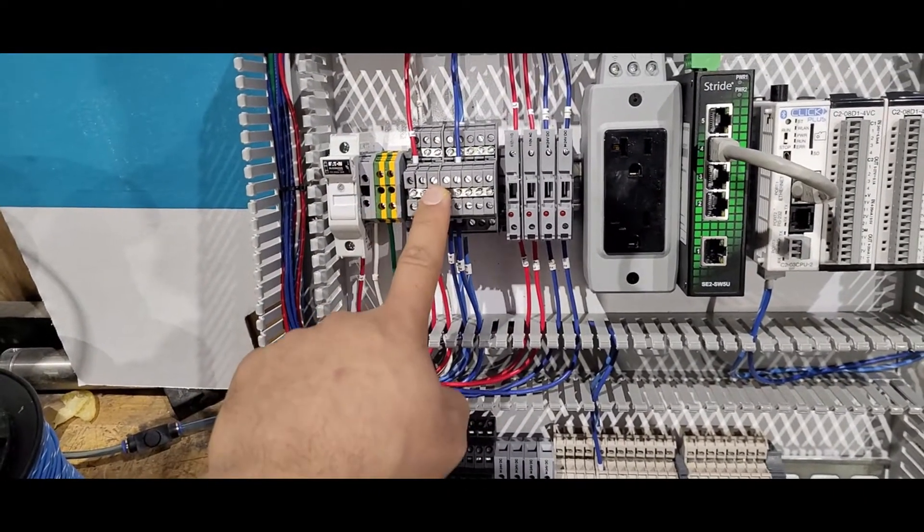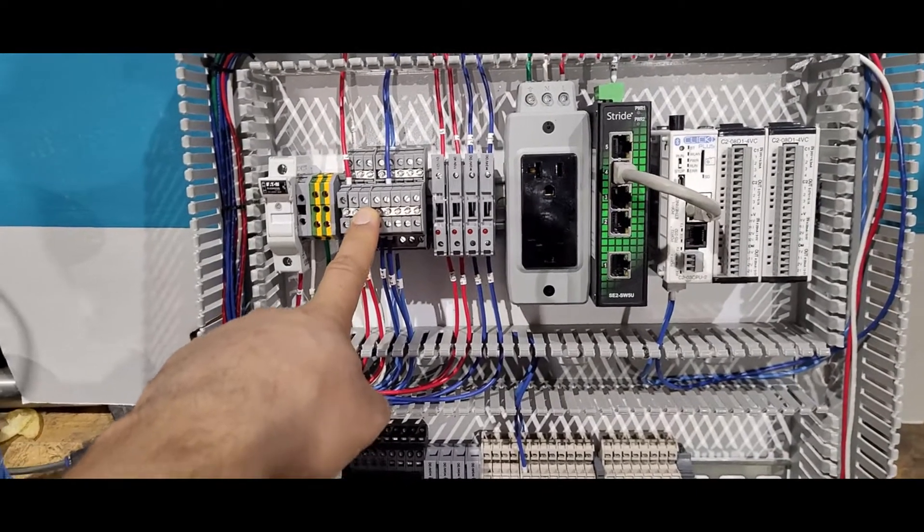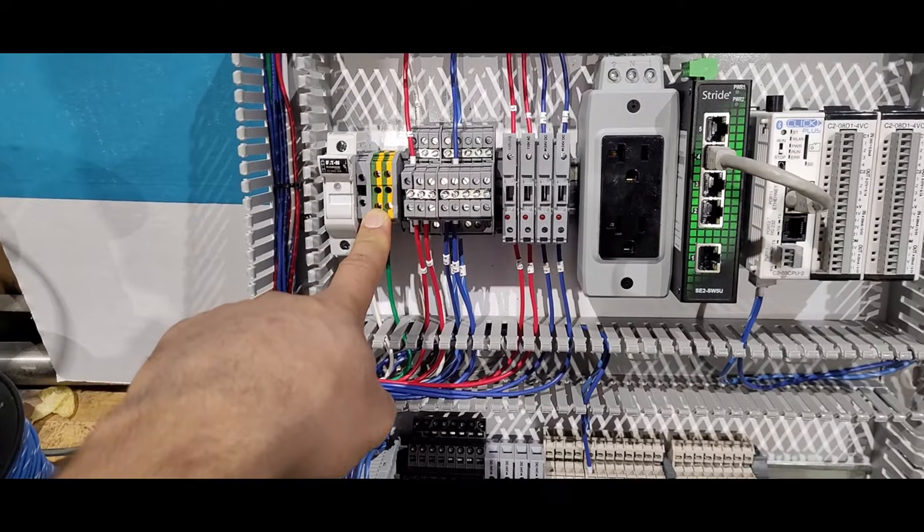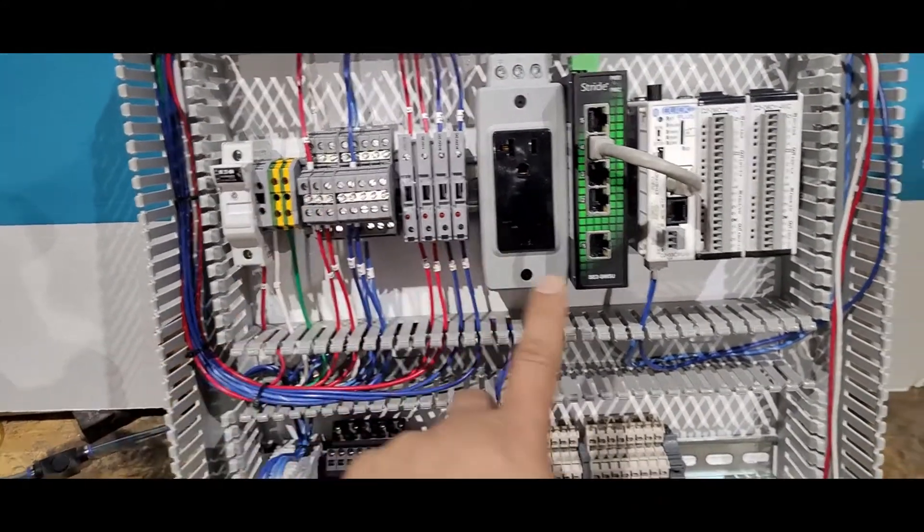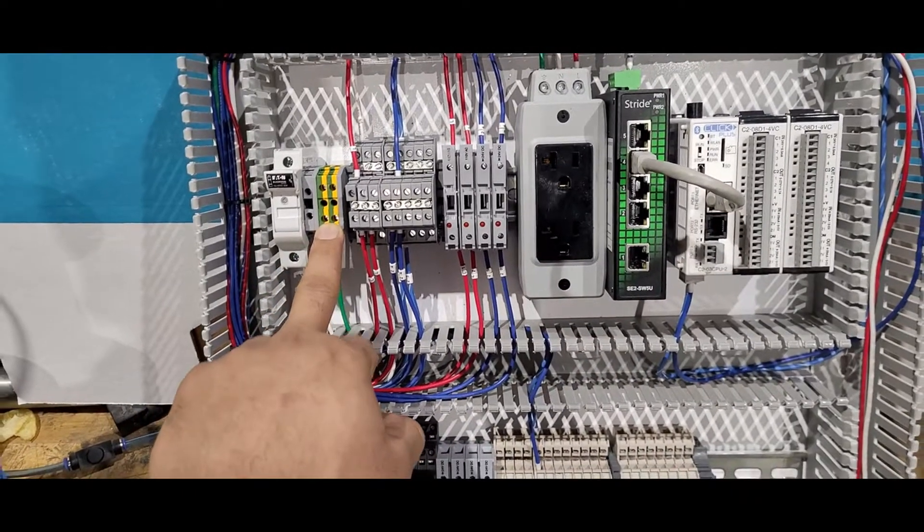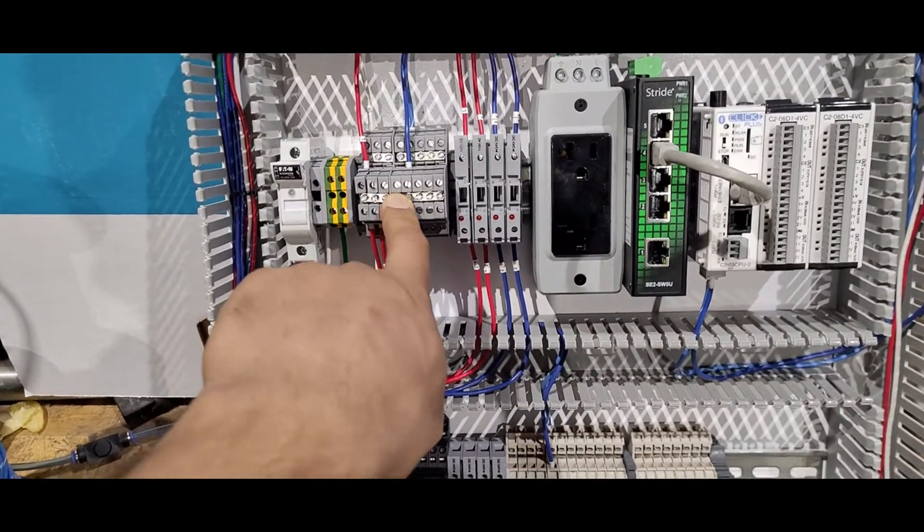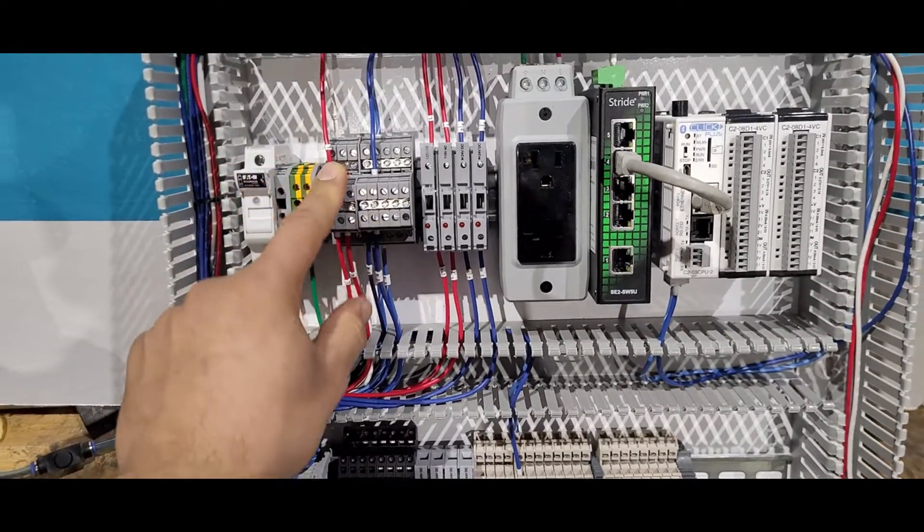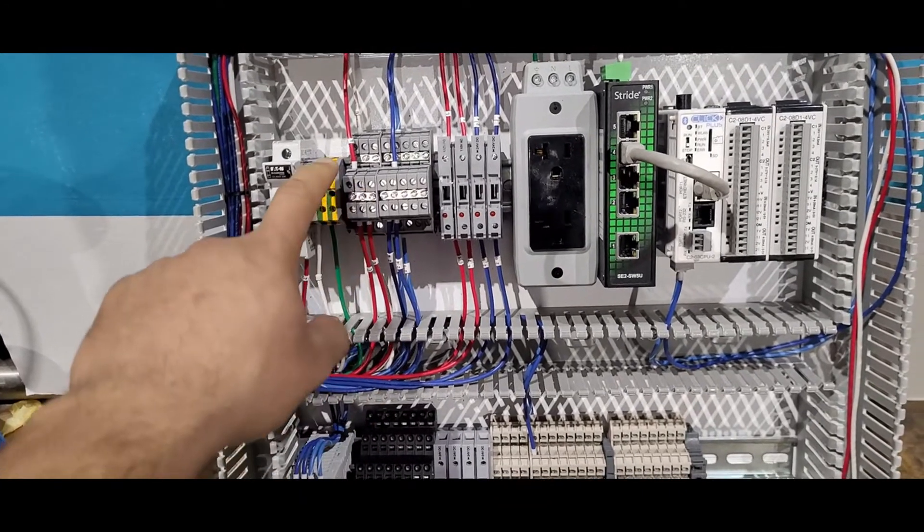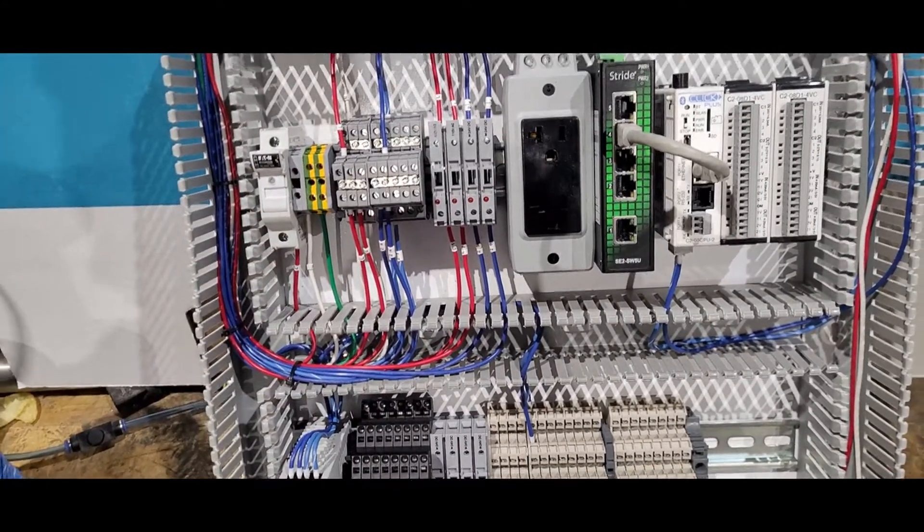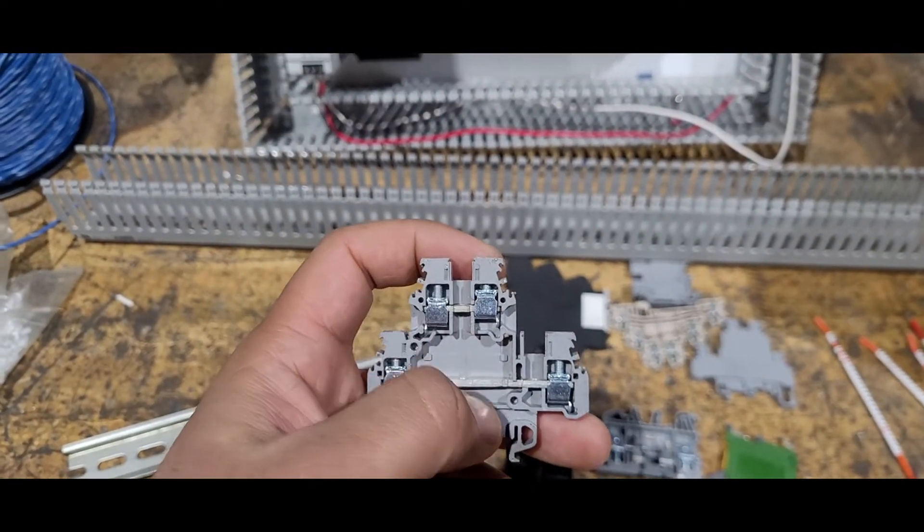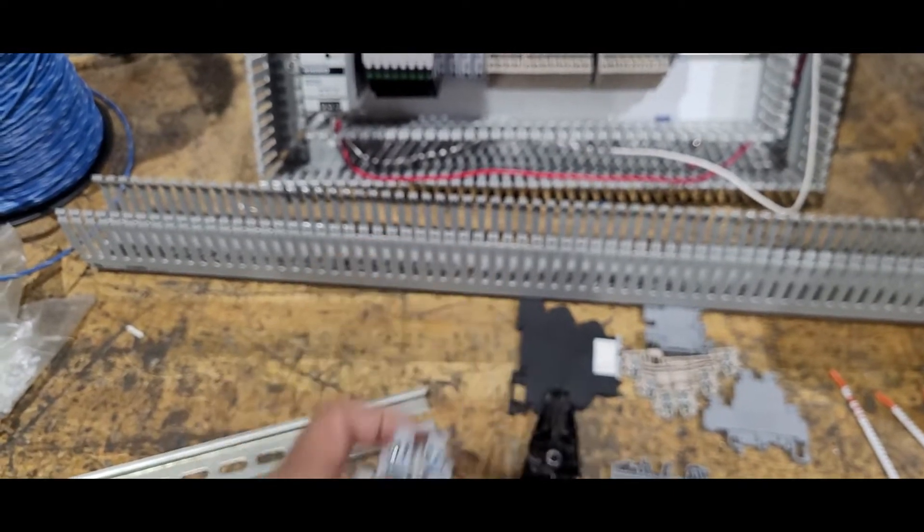These terminal blocks come in different colors and different levels. This green one represents the ground terminals. All the ground wiring on these components will go on this green terminal. Then we have this gray terminal. Gray terminals are basically the junction point of wires where you connect all the wires together. This gray terminal is a two-level, meaning I can put a wire one on the top and one on the bottom.